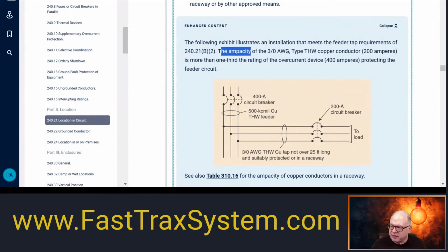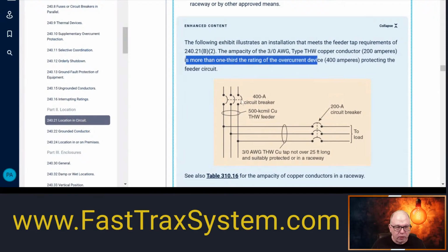The ampacity of the 3/0 AWG THW copper conductor is 200 amps, and it is more than 1/3 the rating of the overcurrent device, which in this case was a 400 amp, okay? More than a third, because 400 amp divided by 3 is 133, okay? So we picked a conductor that was 200 amps. So more than happy here, okay?